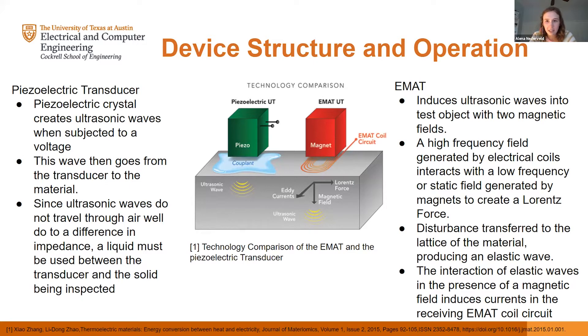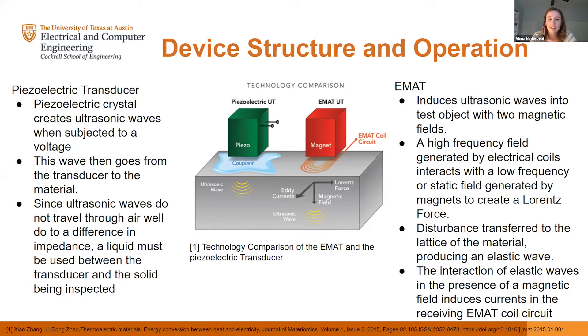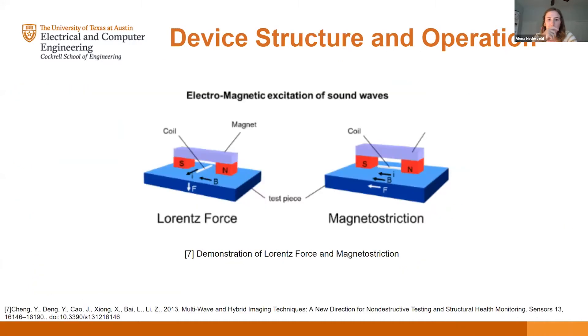With EMATs, an ultrasonic wave is induced into a test object using two magnetic fields. The first is a high-frequency field generated by electrical coils, which interacts with a low-frequency or even static field generated by magnets. This creates a Lorentz force, and the disturbance is transferred into the lattice of the material, producing an elastic wave. The interaction of those elastic waves in the presence of a magnetic field then induces a current in the receiving EMAT coil.